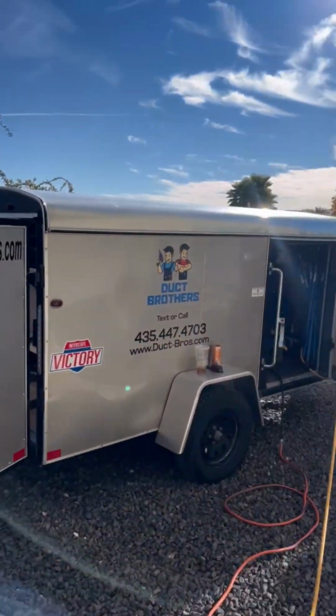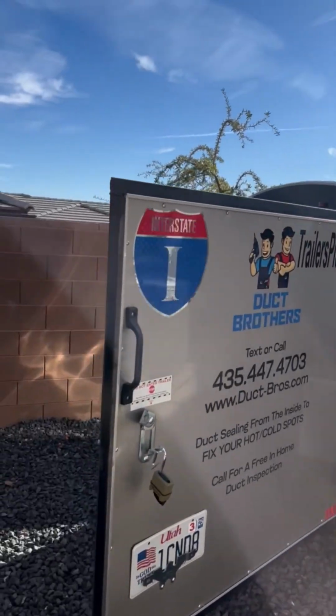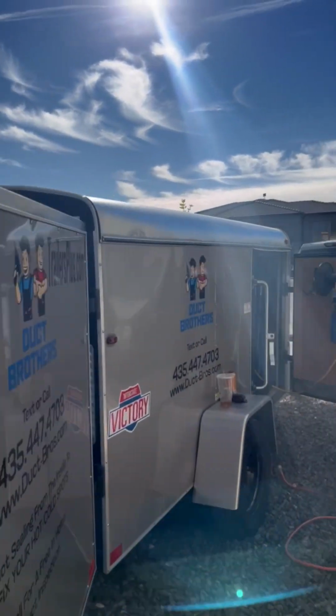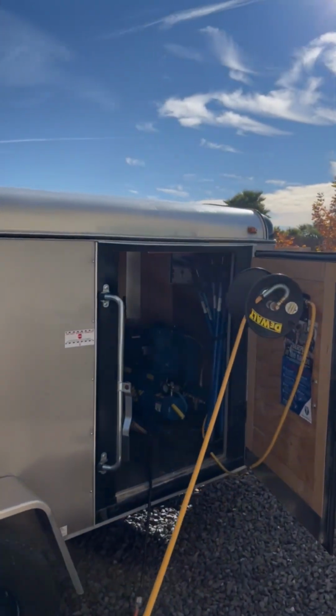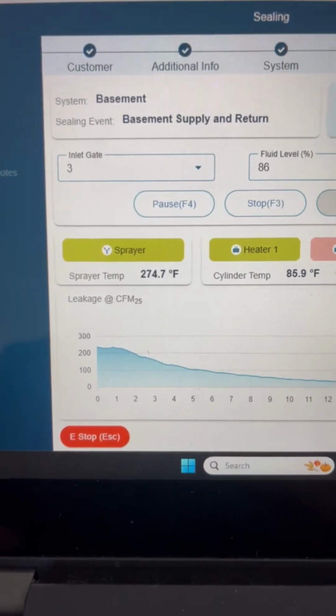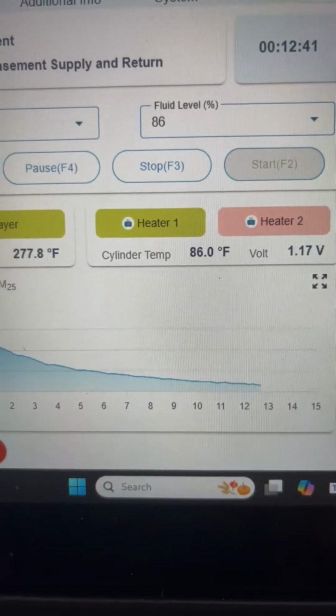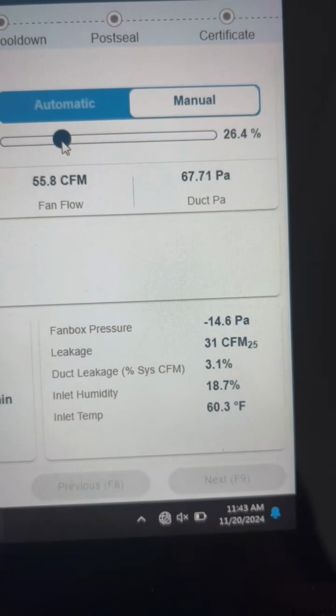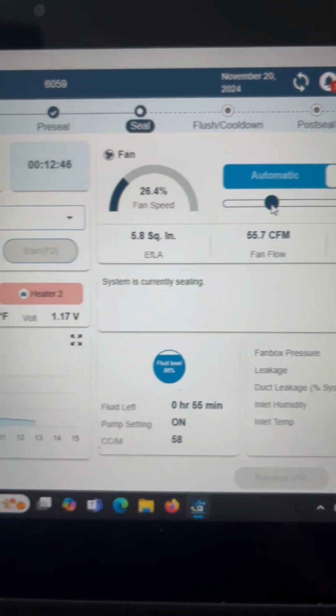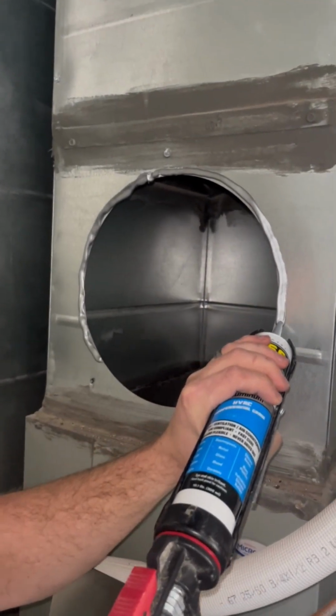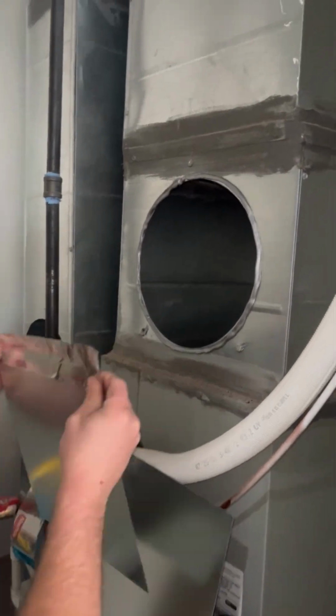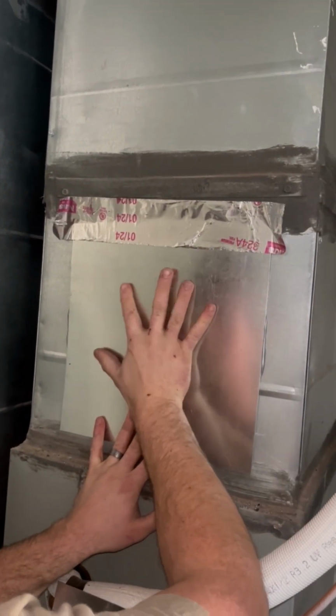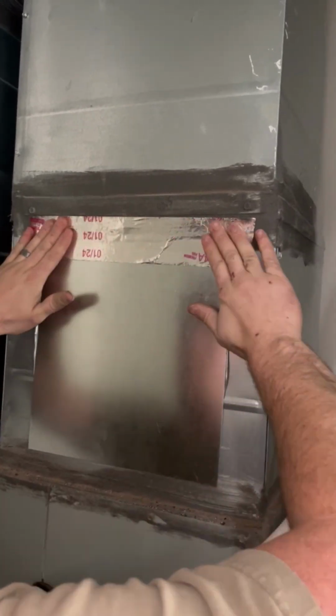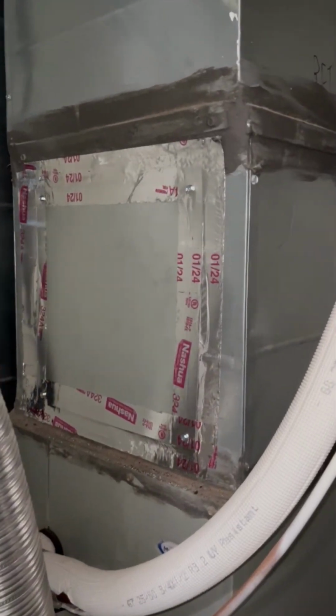This trailer contains all the machinery and tools needed to perform an aeroseal job. The technicians work directly out of the trailer and any of the loud machinery stays here. At this point, sealant has been injected for about 13 minutes. You can see that there's almost no leakage left, only 3% system capacity. After the seal is complete, we use silicone, sheet metal, and some screws to make sure that we have plugged any and all holes created for access. And this is what it looks like after we finished patching up.